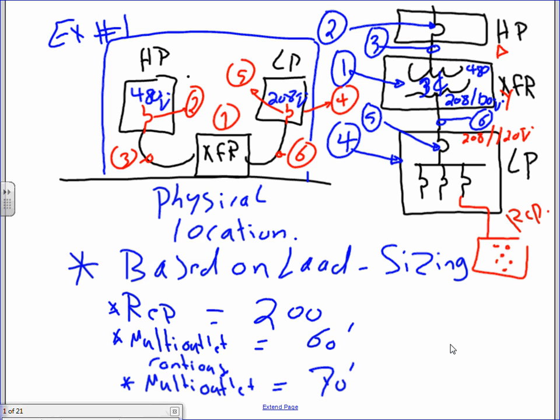And why do we do this? Why do we do it? Because you have to get the 208/120 in a three-phase system, right? How are you going to get 208/120? You need a transformer. Okay, so this is your electrical room. You have what we call a high voltage panel, which is 480. And that panel, by the way, this is your main panel, like the switchgear in our case, the main panel, feeding other things, plus a feeder that goes to a transformer. From the transformer, we go into a lighting panel, a low voltage panel, which is feeding receptacles.